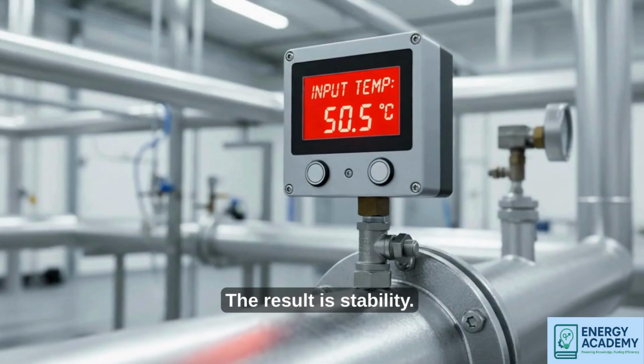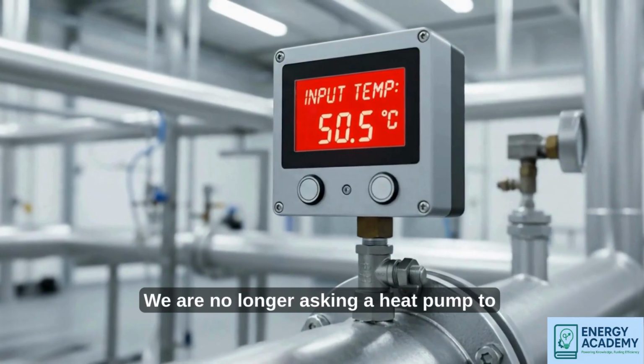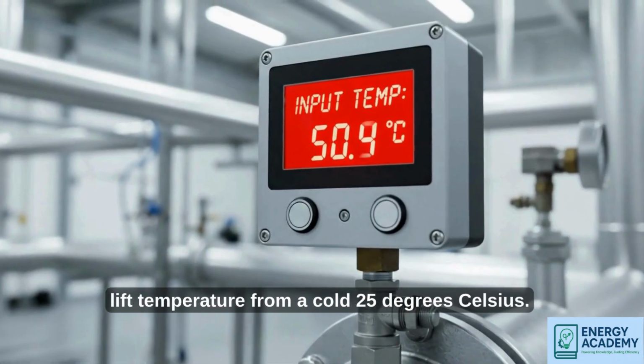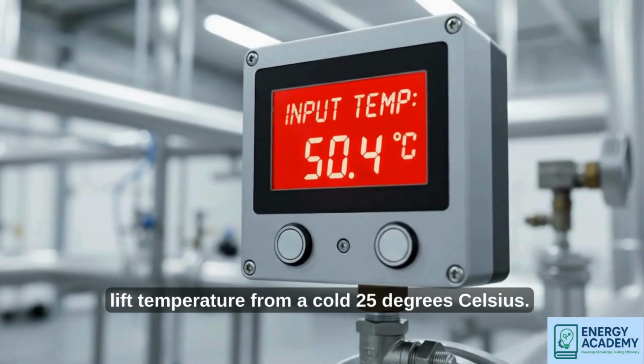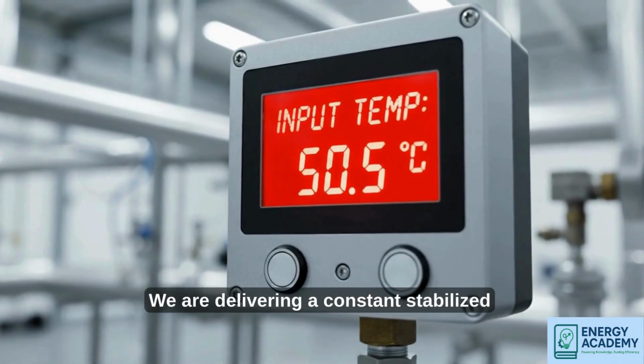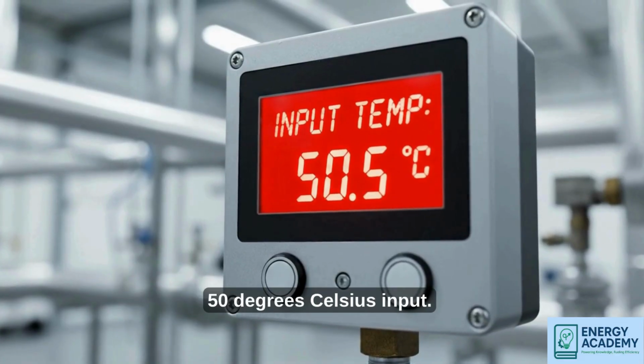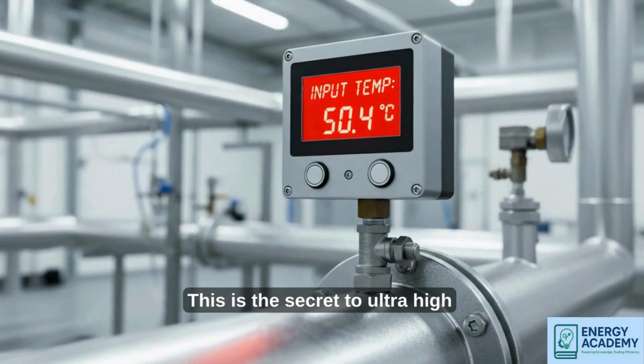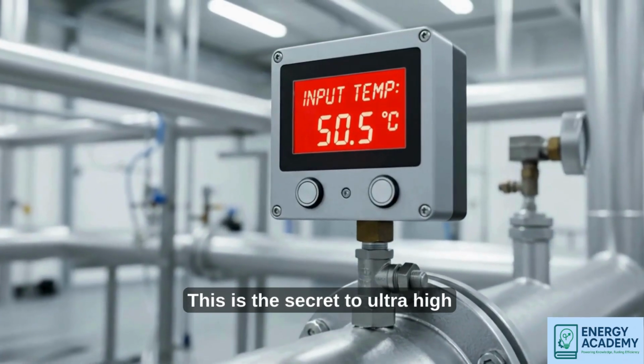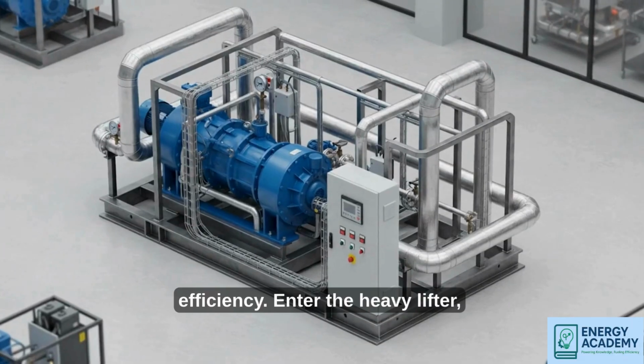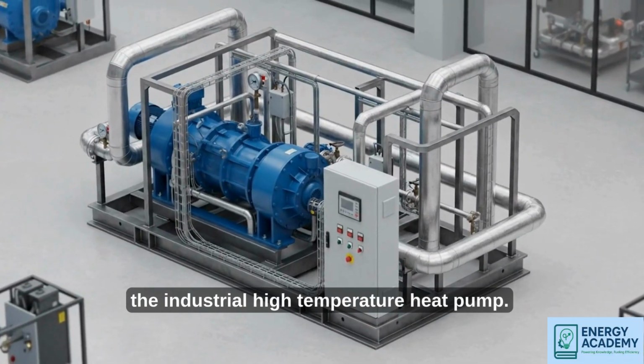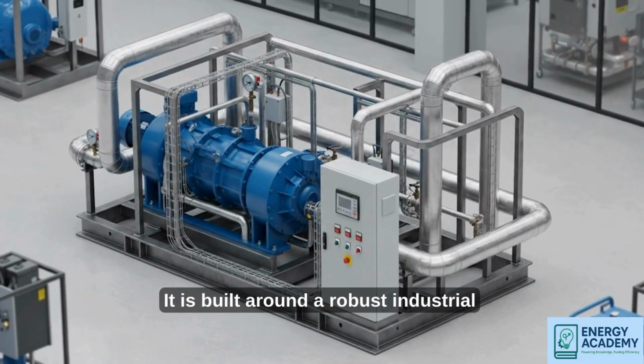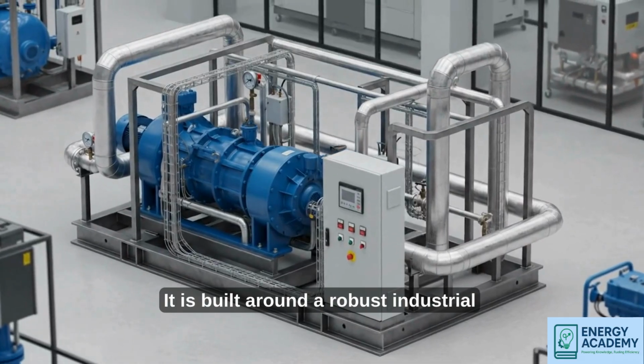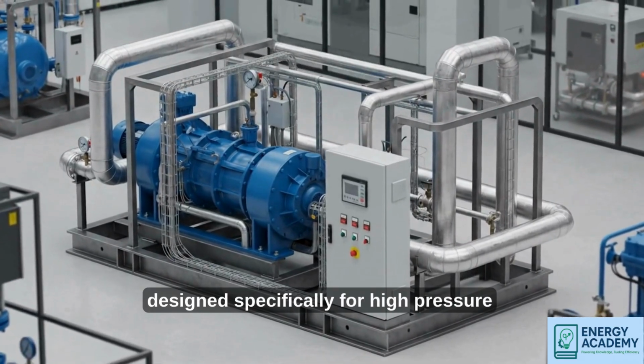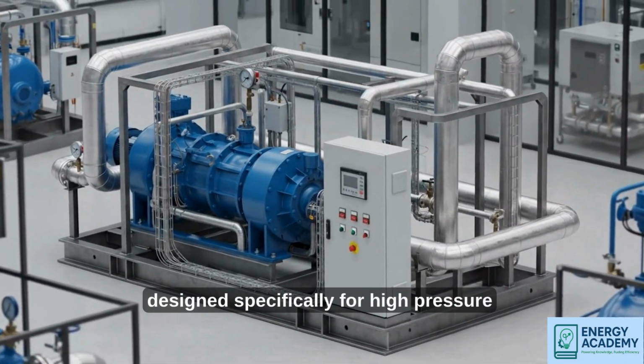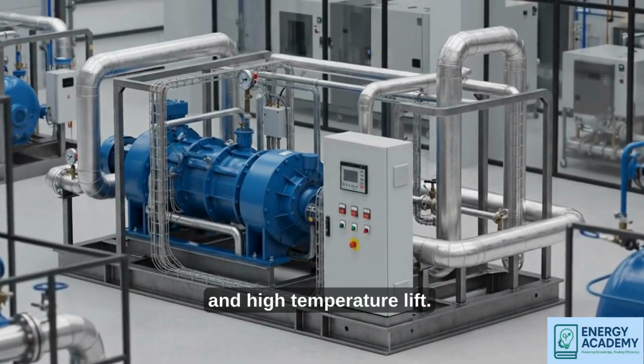The result is stability. We are no longer asking a heat pump to lift temperature from a cold 25 degrees Celsius. We are delivering a constant, stabilized 50 degrees Celsius input. This is the secret to ultra-high efficiency. Enter the heavy lifter, the industrial high-temperature heat pump. It is built around a robust industrial twin-screw compressor designed specifically for high pressure and high temperature lift.